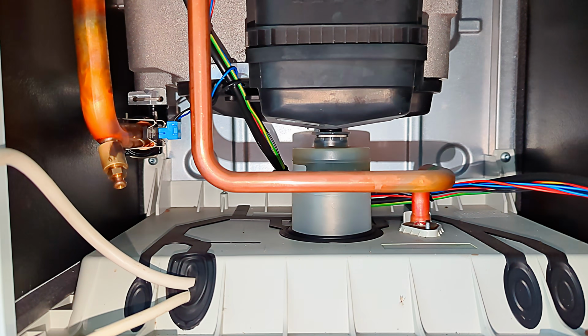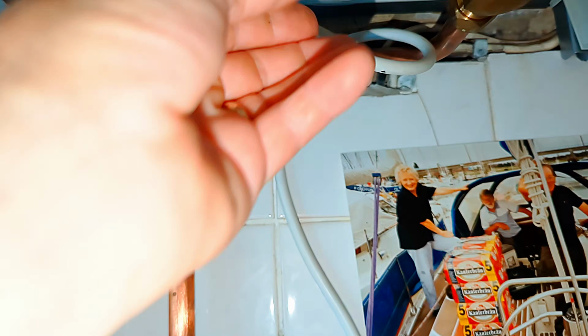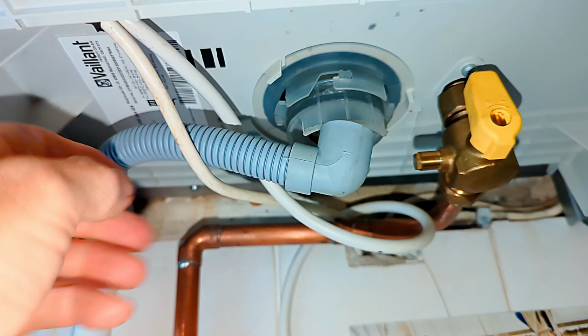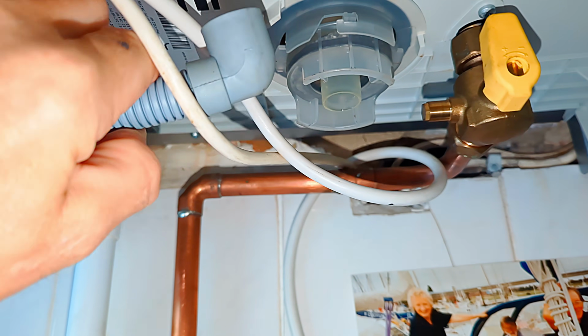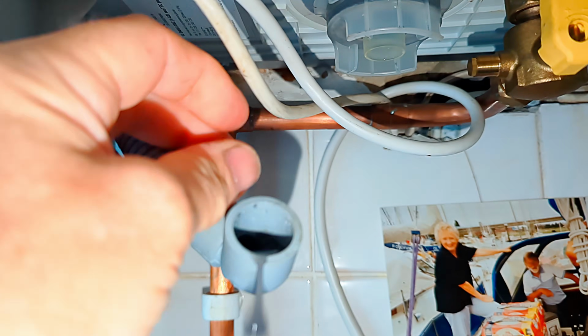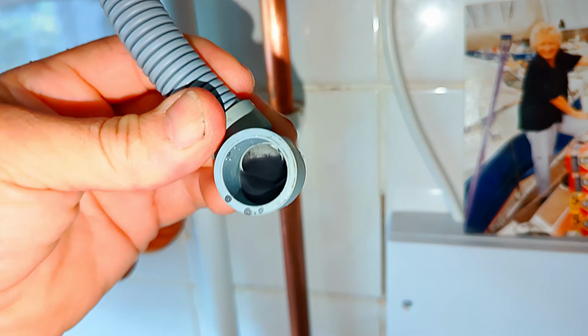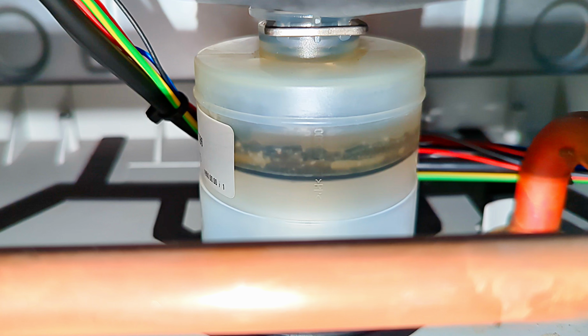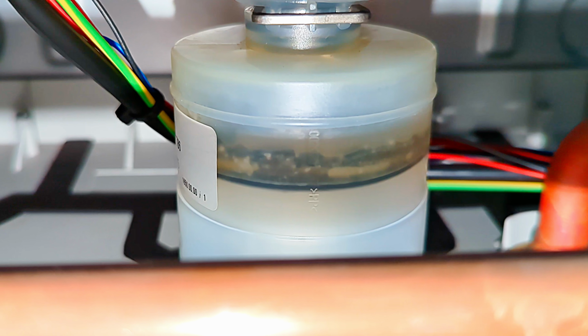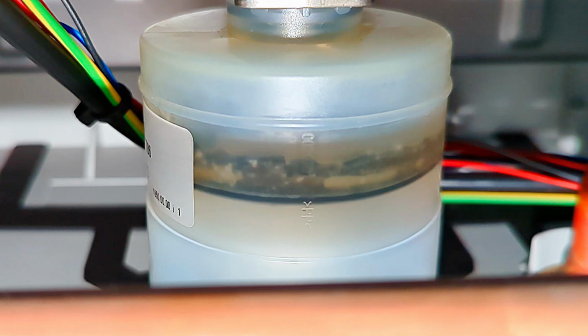Now this clear cylindrical object on the bottom of the heat exchanger is the condensing trap. If we take a look inside this tube here to check that it's not blocked, we can see that's clear as well. Now if we take a look at the condensing trap again, we can see there's a little bit of dirt in there, but it's definitely not blocked up. So what is the problem?